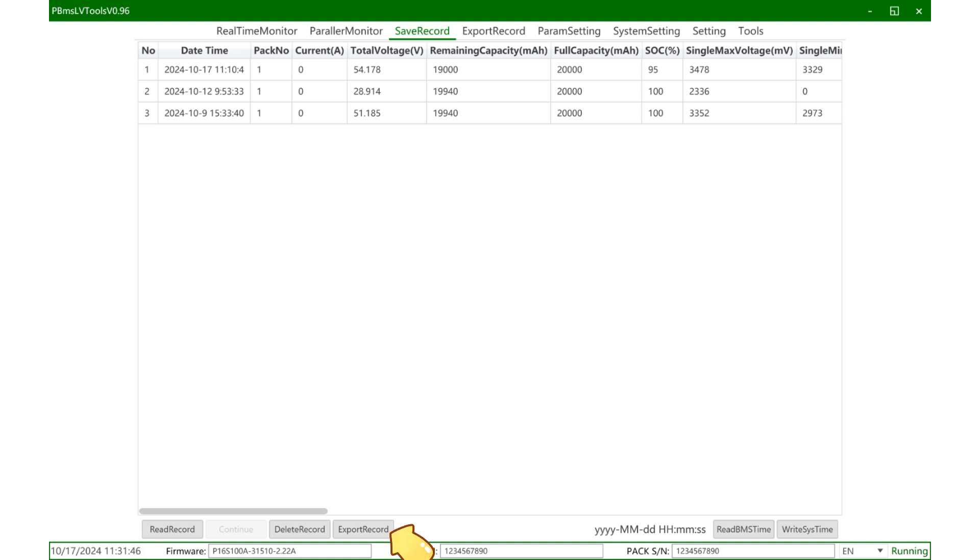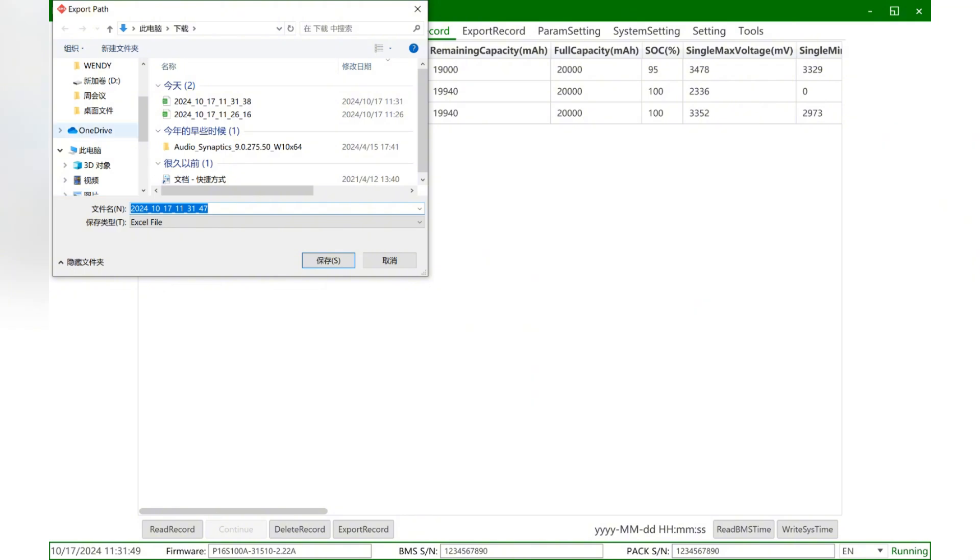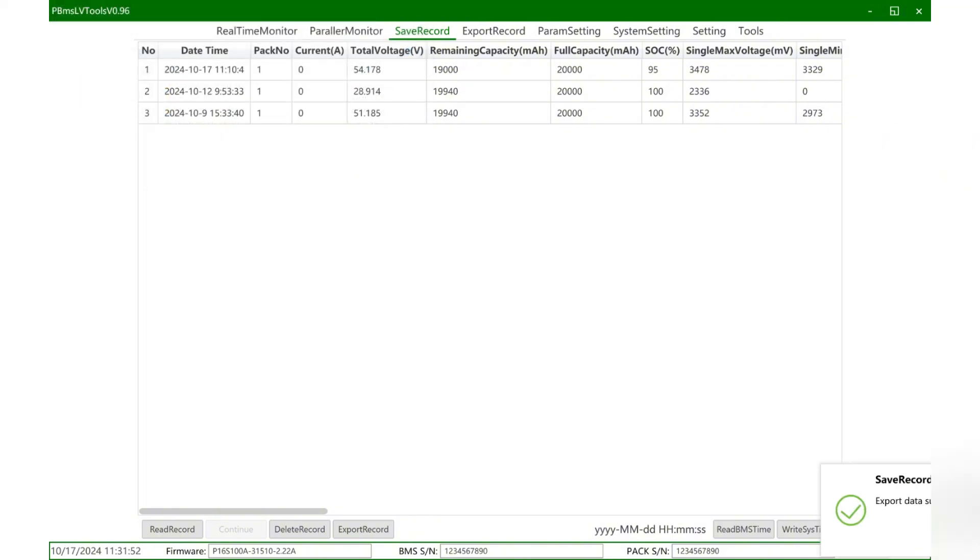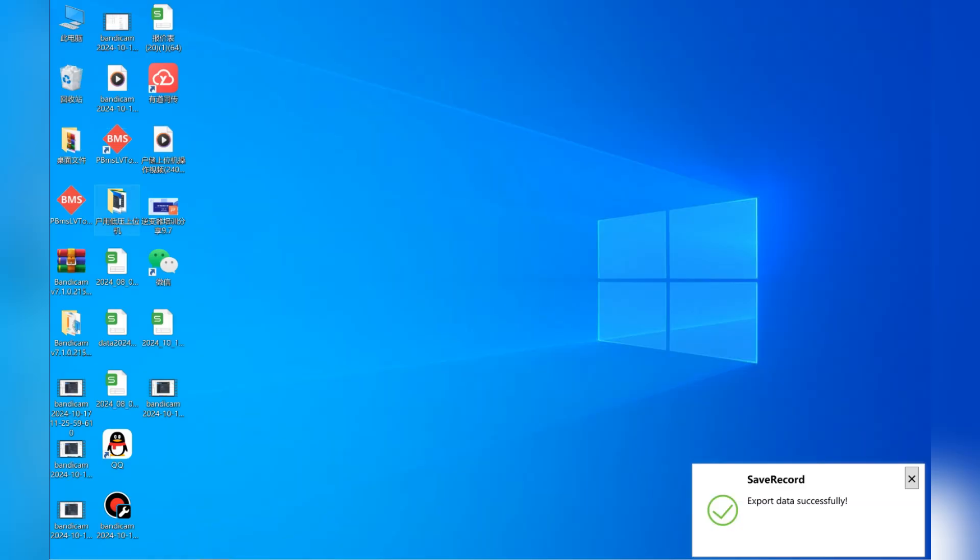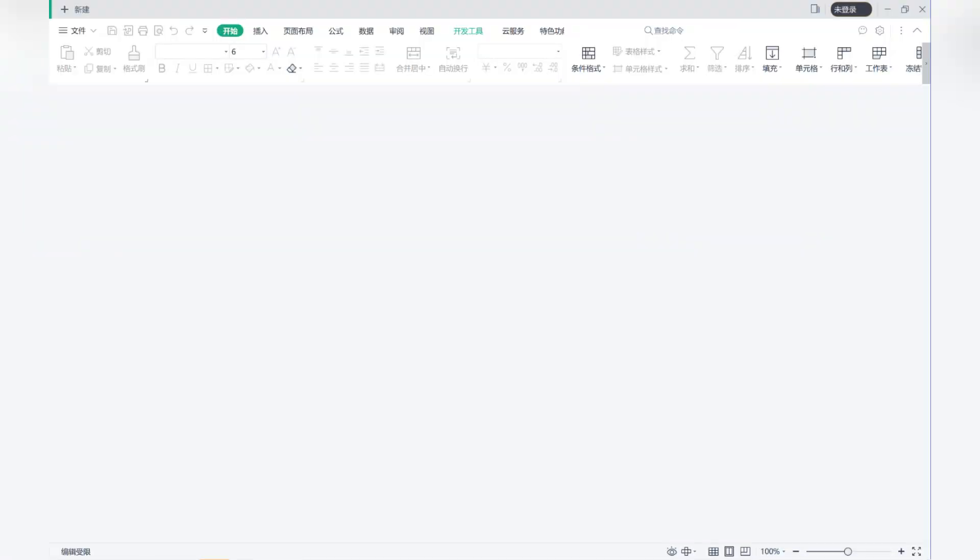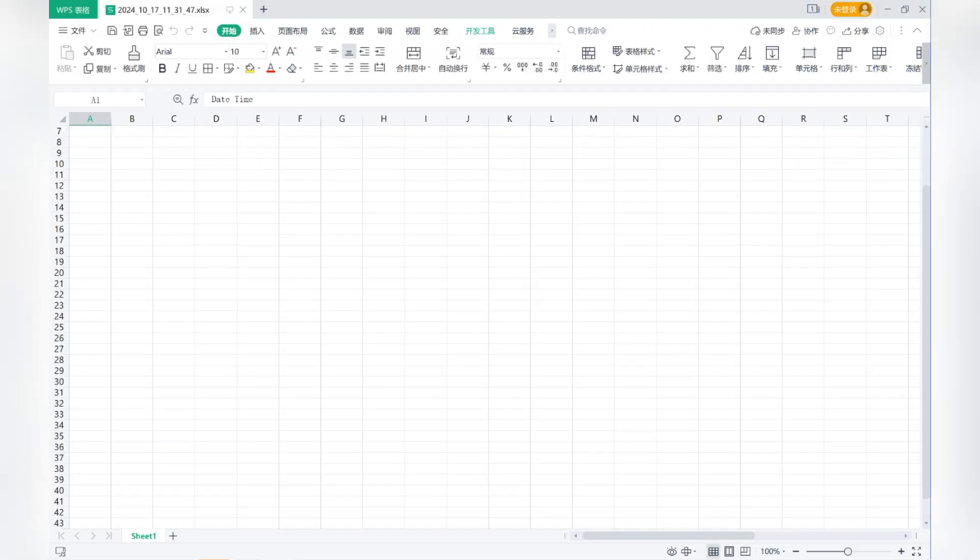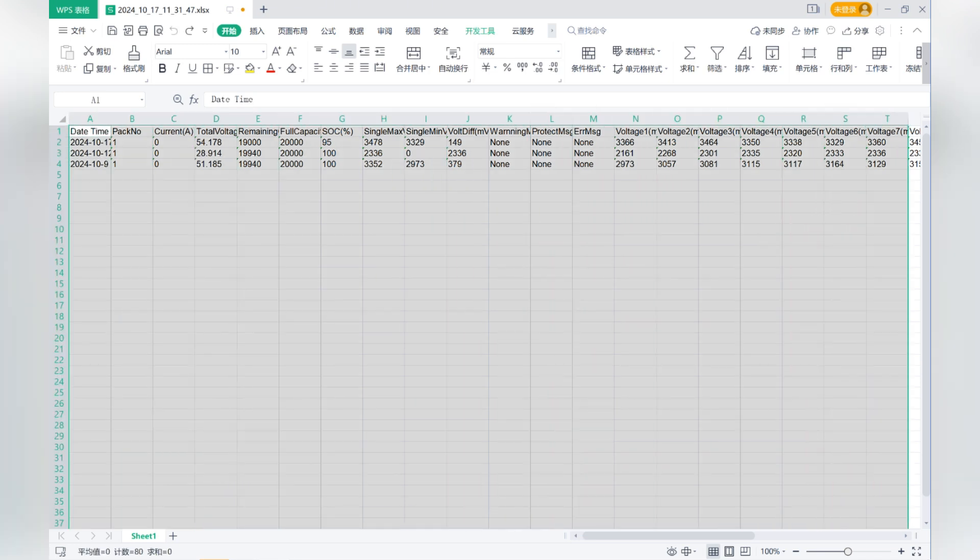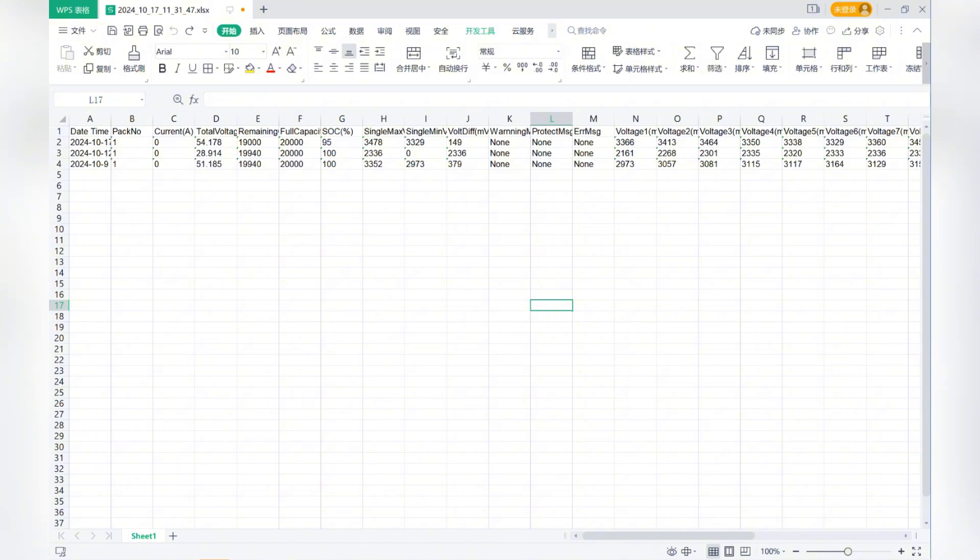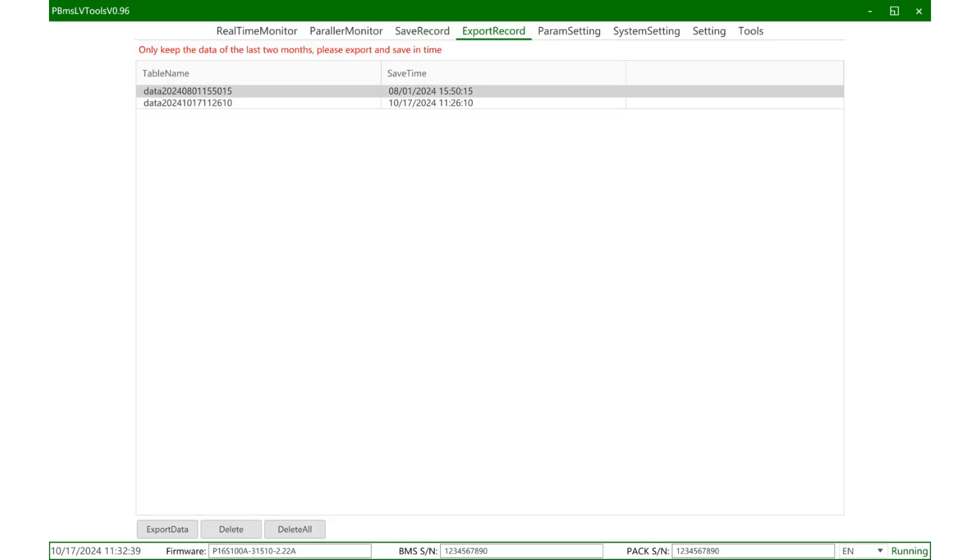Finally, here is the storage information page. It is used to read the historical records stored in the BMS. Generally, fault information, alarm information, protection information will be directly stored in the BMS. When there are some abnormal phenomena that need to be investigated or the cause of the fault needs to be analyzed, the relevant information records are needed. You can read and save them from here. Click export record to create a table. Just click the operation to export, find the corresponding information you exported, and you can see the corresponding records.